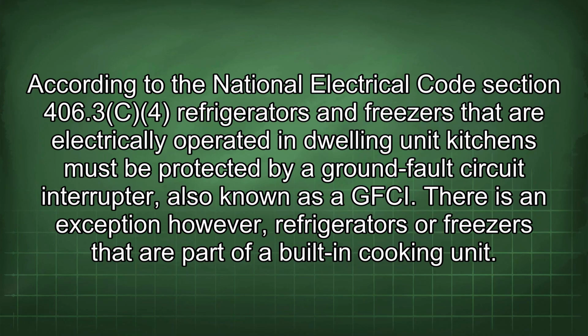According to the National Electrical Code Section 406.3c4, refrigerators and freezers that are electrically operated in dwelling unit kitchens must be protected by a ground fault circuit interrupter, also known as a GFCI. There is an exception, however: refrigerators or freezers that are part of a built-in cooking unit.